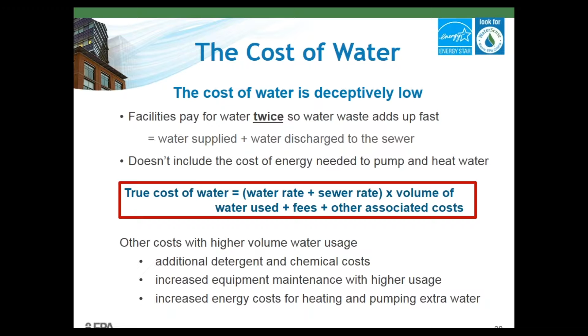So when you're looking at different costs and different projects, you really want to look at the true cost of water, which is the combination of your water and sewer rate times the volume of water used, plus the cost of fees and other associated things. So it can add up more quickly than you think. And other costs can really come with higher volume water usage. These are things like additional detergent, additional chemical costs, increased equipment maintenance because you're using it more, and also increased energy costs for heating and pumping this extra water that you don't actually need to be using.